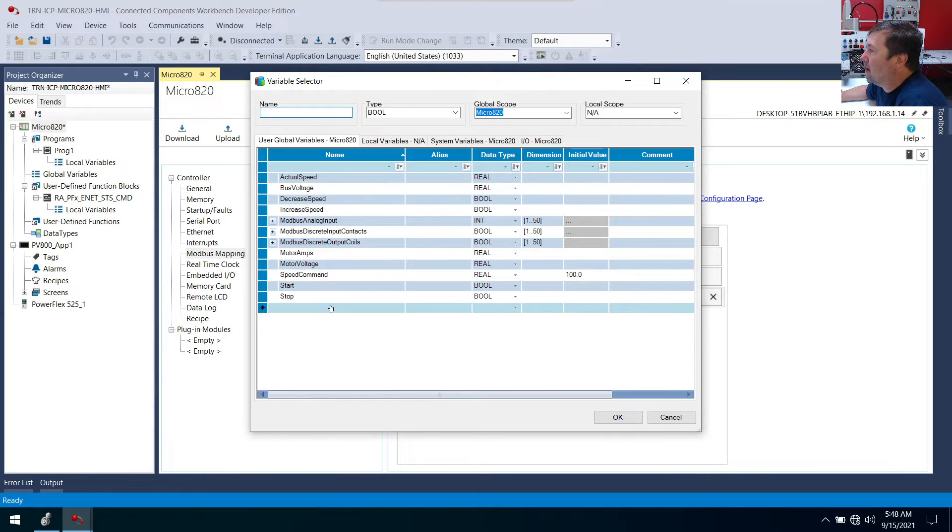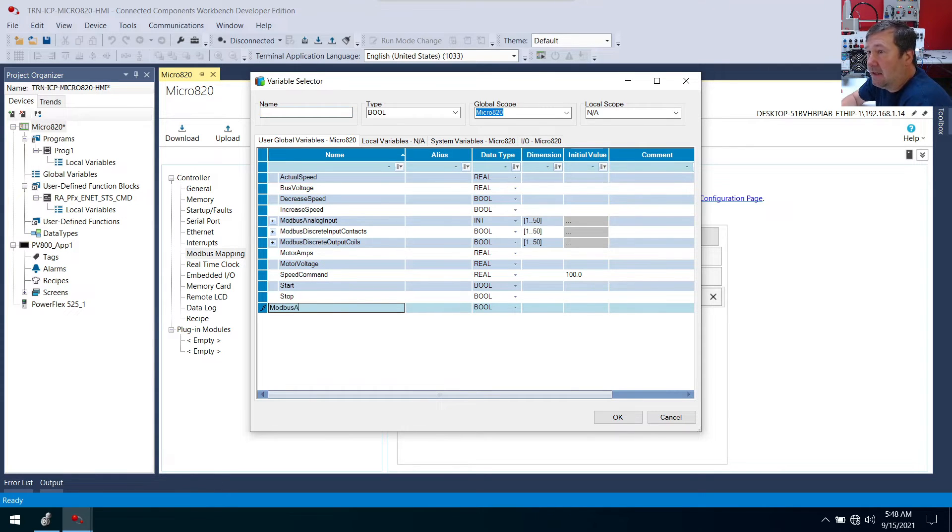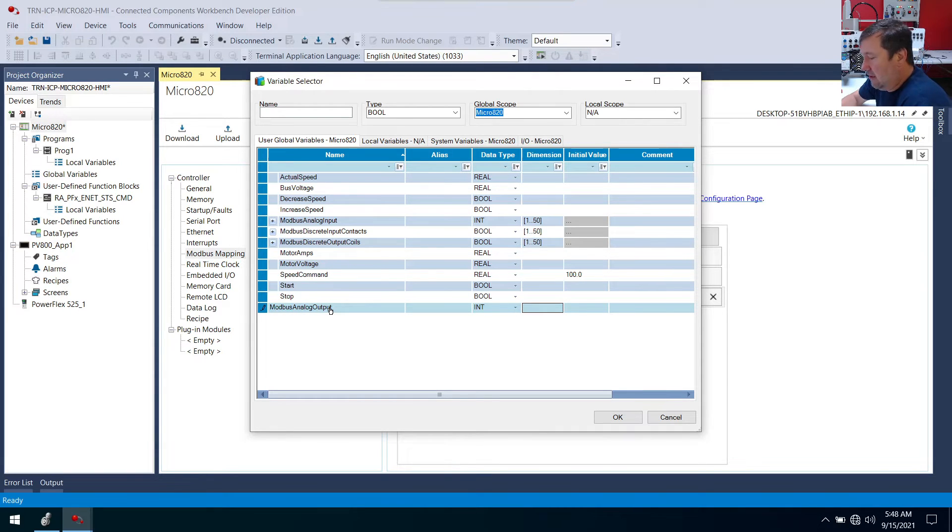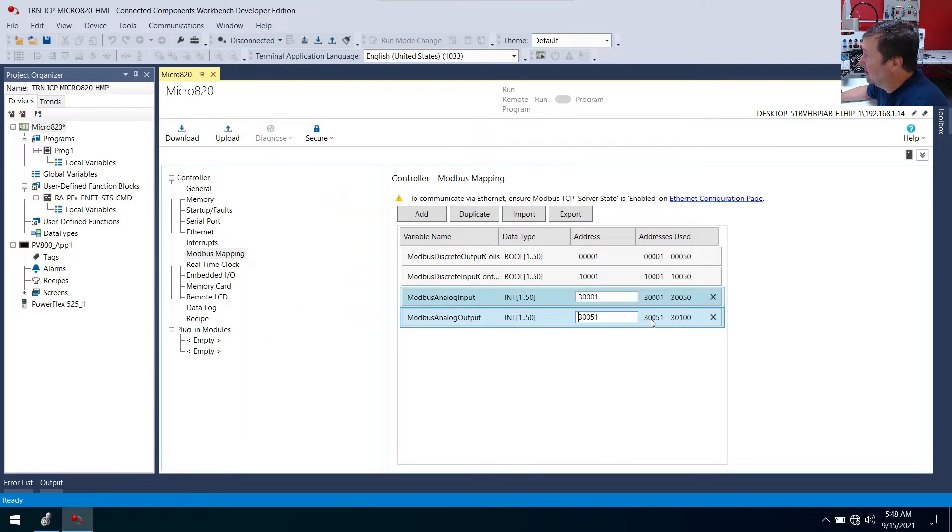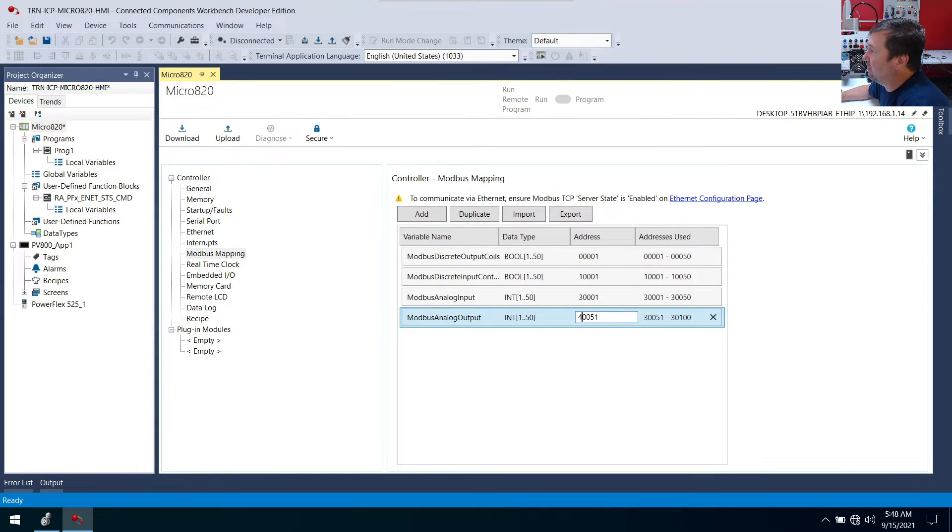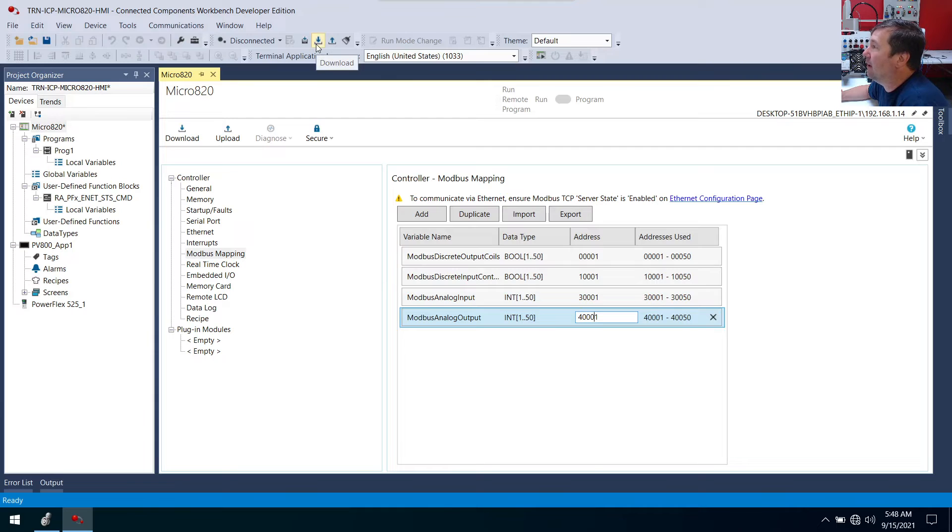We're going to create modbus analog output. And that'll also be an integer. And we're going to make it 1 through 50. And it's going to stack it right behind the last one too. But in this case, usually this one's going to be 40,000. So I'm going to make this 40,001. So that'll be 40,001 through 40,050. And we'll go ahead and download this program.